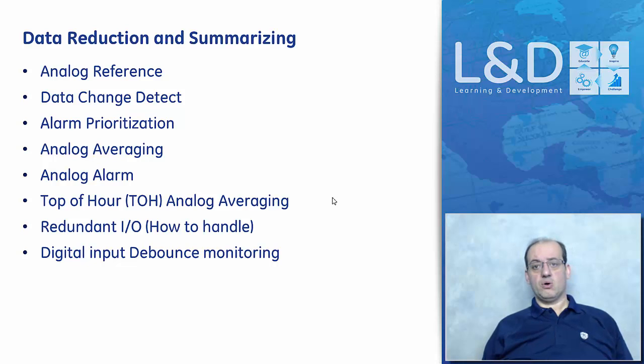For example, ORing all your data, or ANDing all your data, and making sure that you measure the debounce and the data from an averaging point of view, and redundancy of data. You would take the data from two sources, and if they're equal, it means it's trusted data. That all plays a role inside your substation. In substation automation, the more intelligent your data reporting, the more intelligent your operators' decisions.